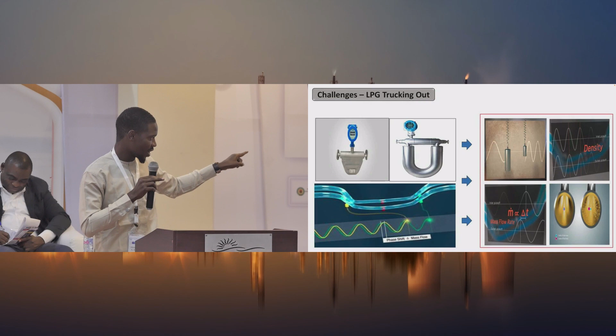it changing into vapor phase, you have this vapor coming into your flow meters. And once this vapor comes into your flow meters, normally you have your center of flow and you have center of fluid. These two need to align for you to have accurate reading. The moment you have vapor in this flow meter, maybe your drive gain is above 3.7, then you are in trouble. Because the center of mass is going to change, and the flow meter is going to shift by itself, and you have a reading. And then you explain where that product goes to.